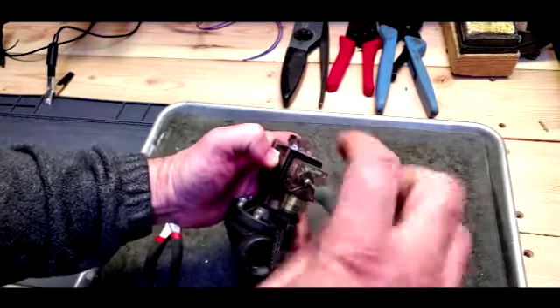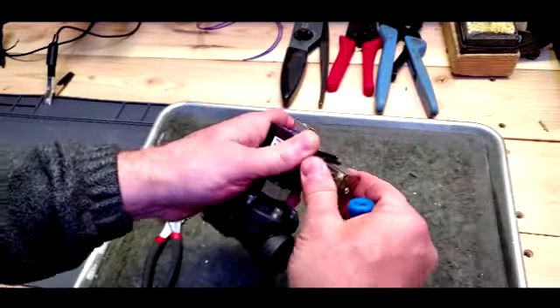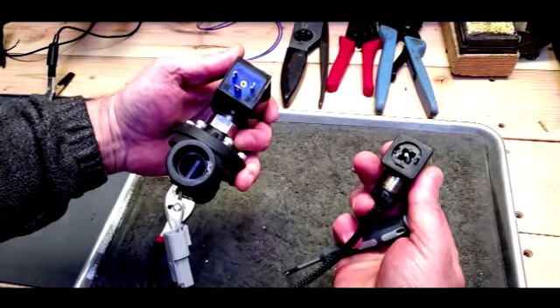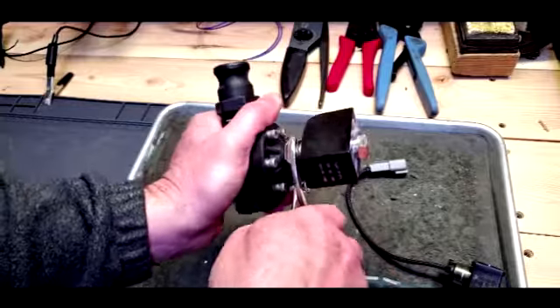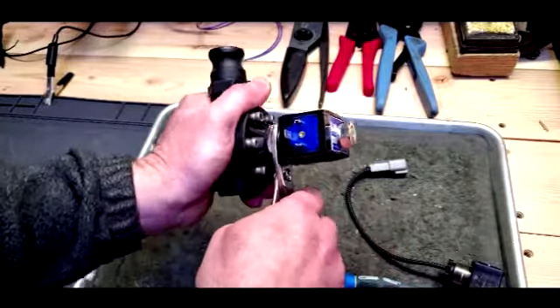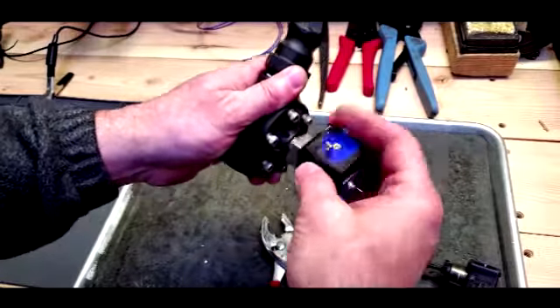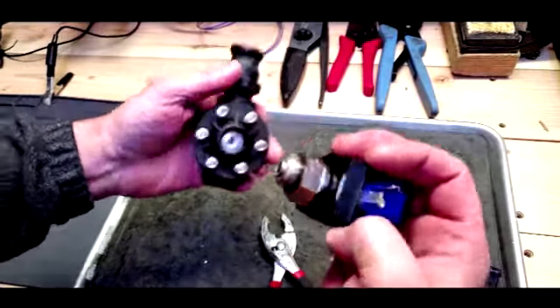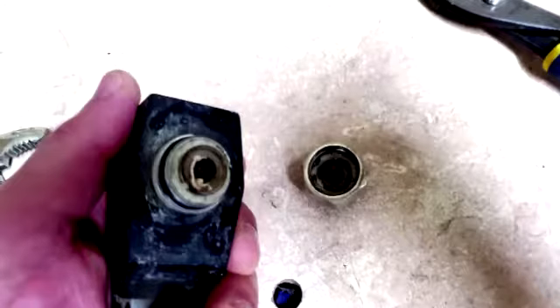Now I did this off the flow meter, but you can do it on it just as well. You can disconnect right from the harness, or you can take off this cap at the side. It's good to check this once in a while, make sure it's not corroded - everything looks good. I'm going to grab this nut at the bottom and we're just going to take it right off. Be very careful because you have stainless steel and plastic together. Pull that out - that exposes your diaphragm and also exposes the inside.